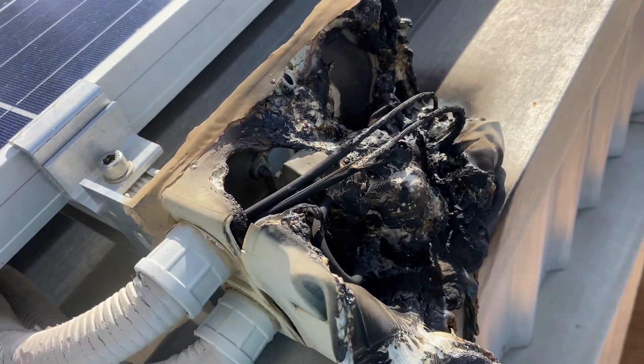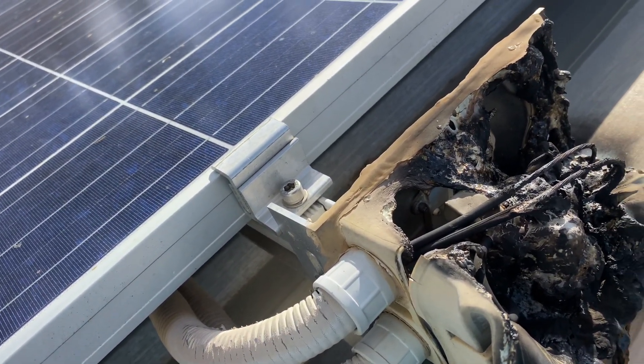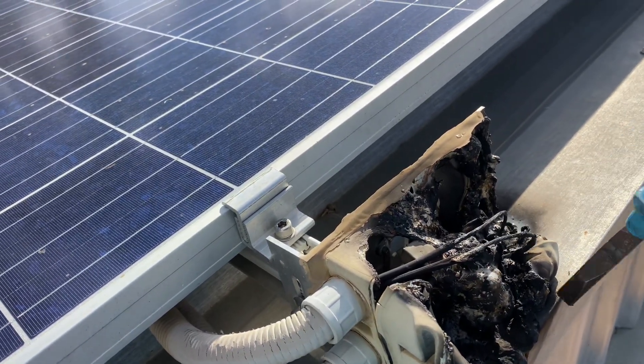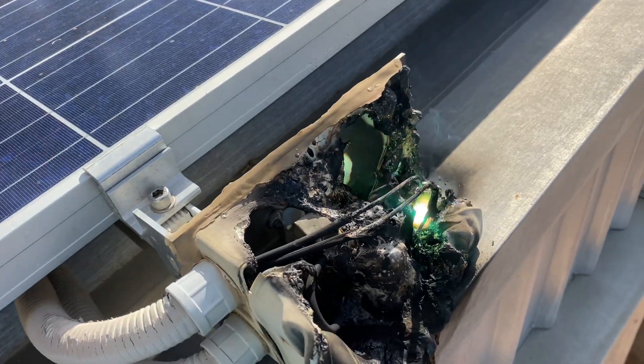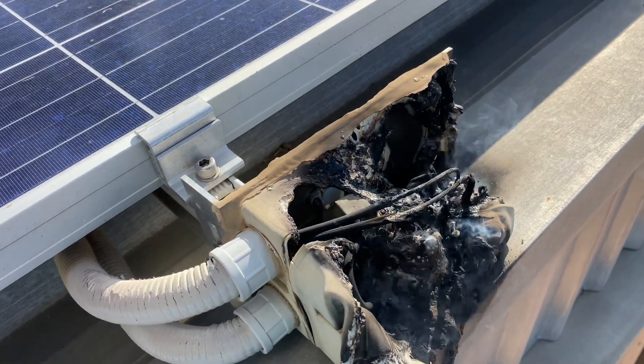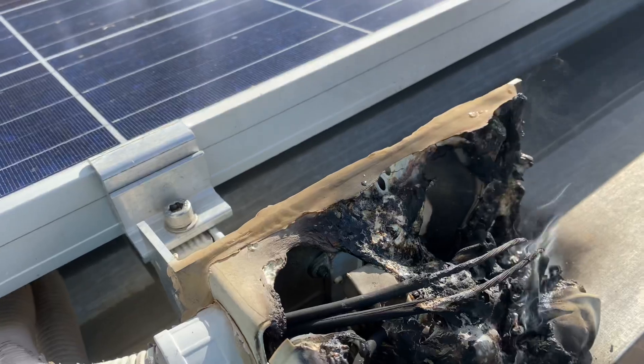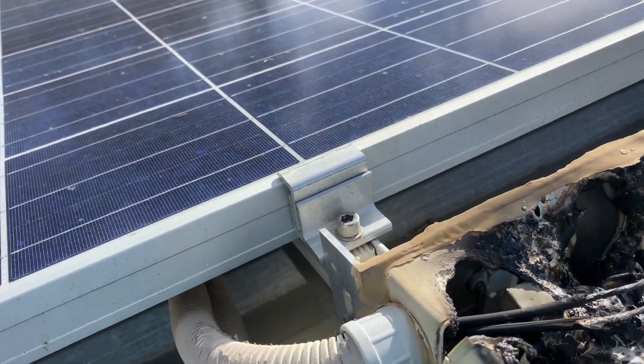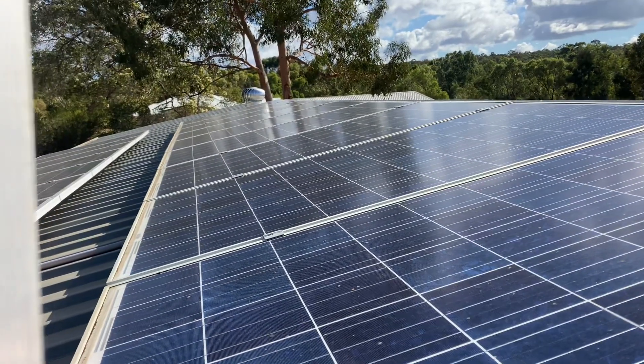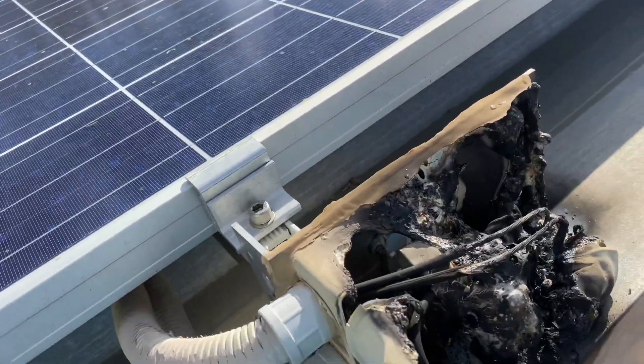Like I say, that is still alive. Let's have a bit of a look. There we go — still alive, even though everything's shut down. So that's what you need to be careful of. And now it's not short circuited, there's no current at the moment. So I'm actually going to unplug one of those leads on the array, and that will make it safe for me to work on.